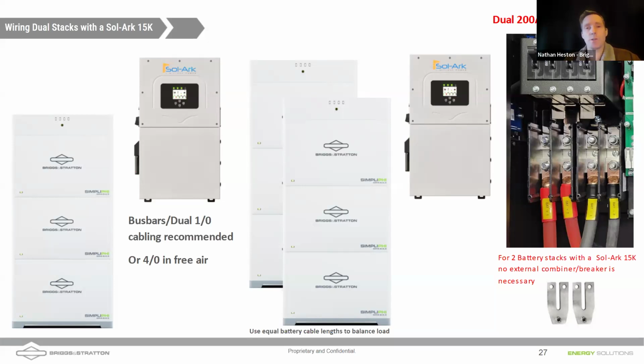You could do two stacks, or quarter stacks if you don't have the height available at your installation location. We're showing here the recommendations for your home run DC battery cabling. When installing within conduit, our recommendation is dual 1-aught battery cables for a single stack, and if you've got double stacks, run two 2-aught cables. You've got 200 amp dual cable breakers in the Sol-Ark to protect those battery cables. If you need to combine them into one because you've run a single set of 4-aught for an open air single stack with a Sol-Ark 15K, we do sell those combiners for about $25 a set.